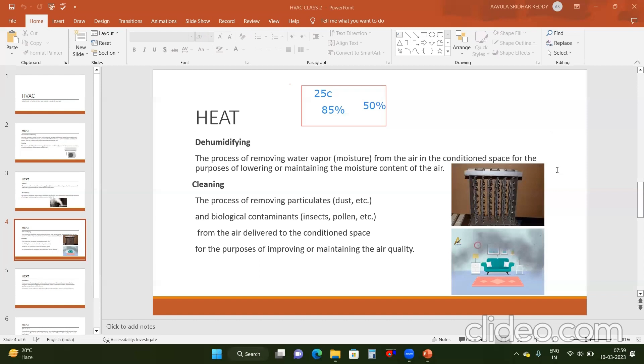So next one is cleaning. What is cleaning? Cleaning is the process of removing particles, dust, etc., and biological contaminants, insects, pollen, etc., from the air delivered to the conditioned space for the purpose of improving or maintaining the air quality. We have discussed that every room requires some outside fresh air, that is 10%, or more or less than that, based on our heat load calculation. When we take outside air and filter it before taking it inside, we call that fresh air. Remember this term for all the next classes.